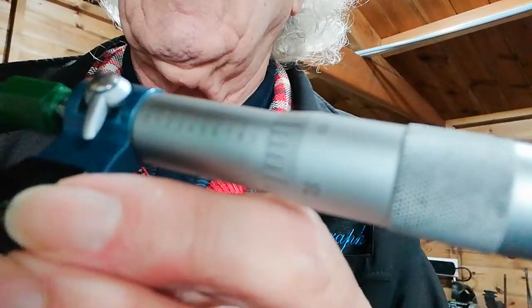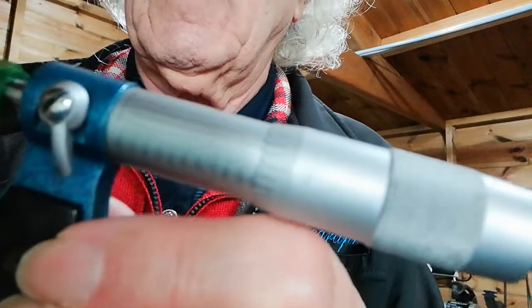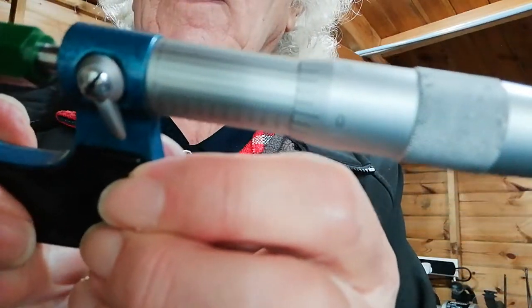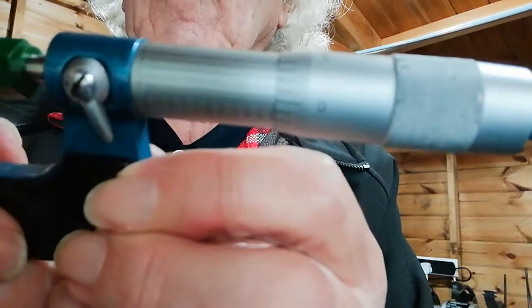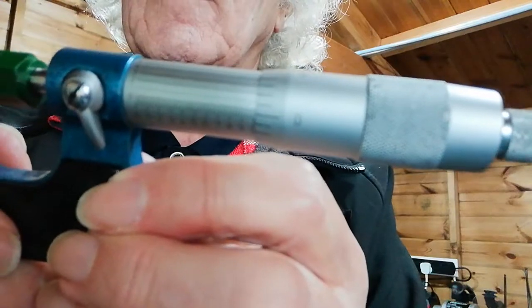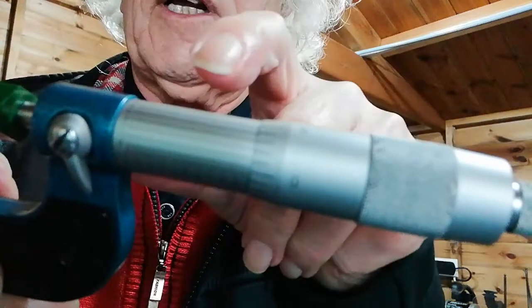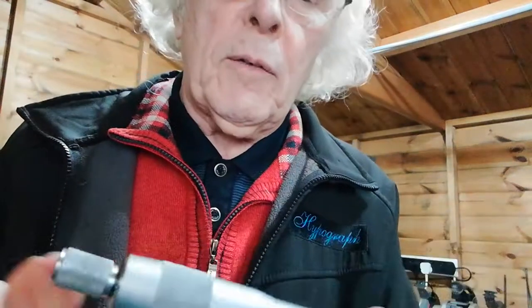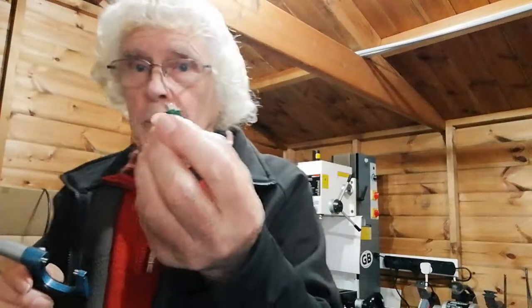So difficult. Anyway, there you are, that's better, look. And you'll see that third one. 1, 2, 3. On that line there, on this line here. So that tells me it's 3 thousandths of an inch out. Okay. So if ever you've wondered that you've got a micrometer not calibrated, and you think this doesn't seem right, well, that's how you find out, by getting these calibration bars.